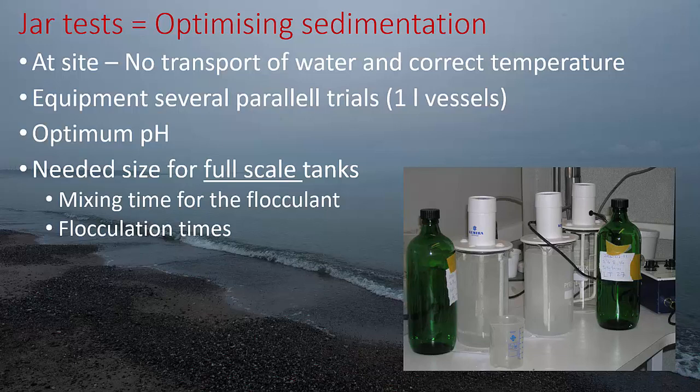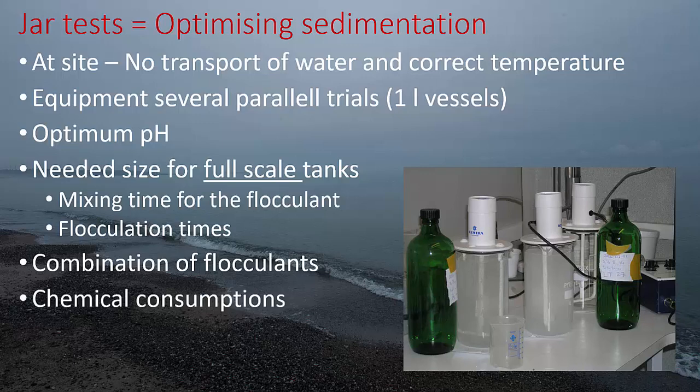If you need ten minutes or five minutes for the flocculation time, you may need to double the volume of the flocculation vessel. You can test combinations of flocculants — metal flocculants and polymers. You also get a very good idea of how much chemicals will be consumed, and an estimation of surface loads, which is what you need to design the sedimentation. Within this small one-liter jar test you can get a pretty good idea of the surface load.